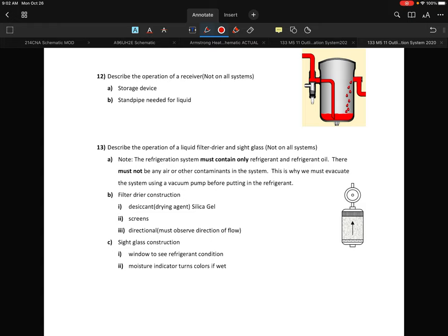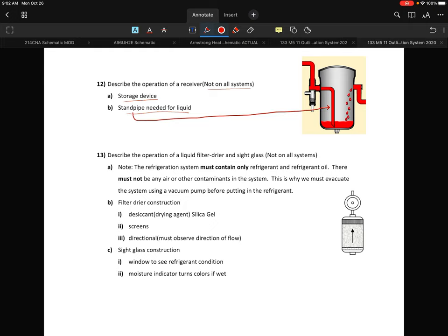Now we're going to move on to item 12 — describe the operation of the receiver. We had mentioned this earlier — it's not in all systems. It is essentially a storage device. There is a standpipe in it that's needed for the liquid. The standpipe is going to pull the liquid off the bottom. If the refrigerant level in the receiver is higher, that pipe will always be pulling off the bottom, and if it drops a little, it's near the lower part. It's really just an extra storage container.